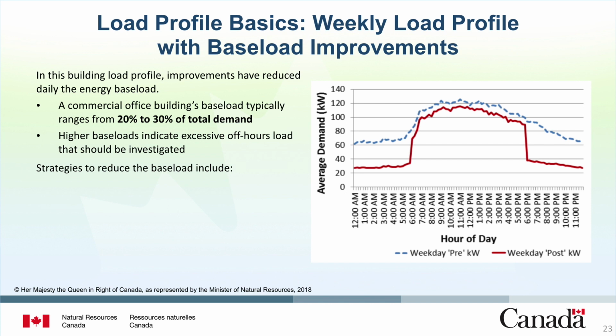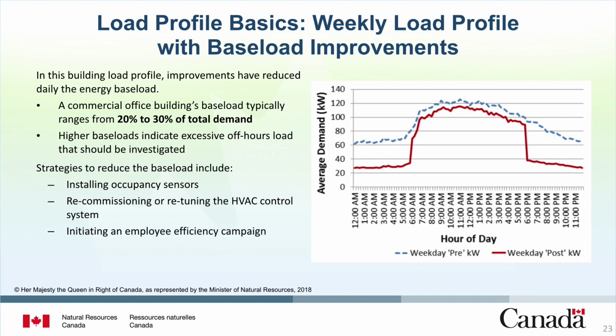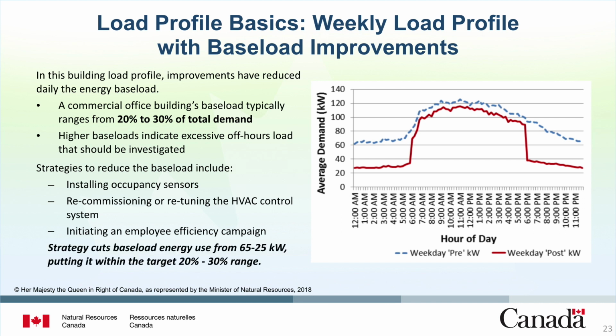Strategies to reduce the base load include installing occupancy sensors to reduce electric lighting and plug loads left on during unoccupied times, recommissioning or retuning the HVAC control system to correct scheduling and set point issues, and initiating an employee efficiency campaign to engage occupants in energy-efficient behavior. These strategies target baseload energy use as well as occupied and peak energy use. In this example, these types of strategies cut baseload energy use from 65 to 25 kilowatts, putting it within the target 20 to 30% range.